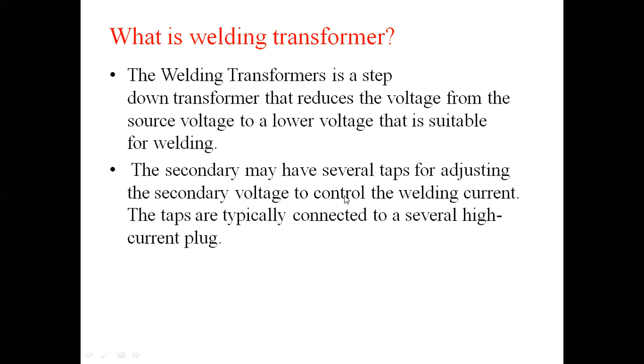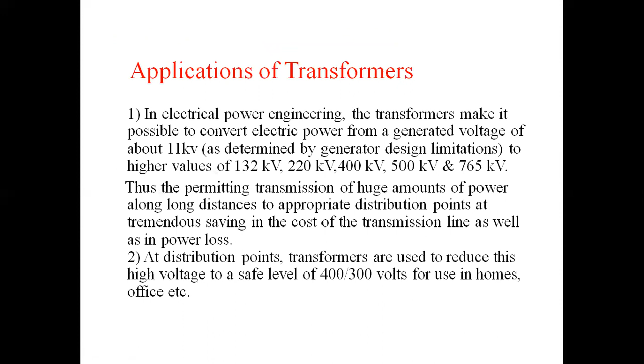This is to control the welding current. The tappings are typically connected to a high current plug. The transformer which is used for welding purposes is named the welding transformer. In a welding transformer, high current values are used, and for different metallic parts we need different current, since not all metallic parts use the same temperature or heat. So in order to provide the required current value, there is an arrangement with several tappings on the secondary winding to adjust the secondary voltage and control the welding current. It shows the figure of the welding current.